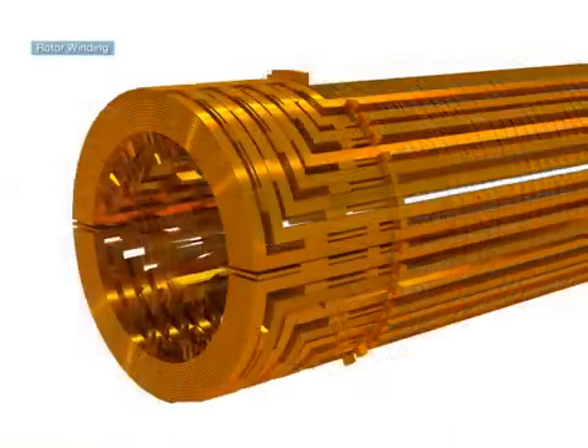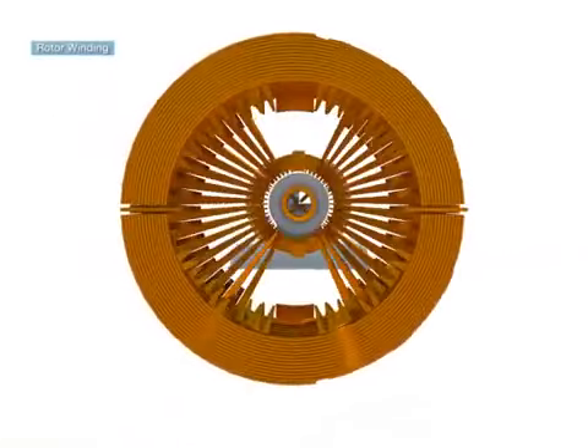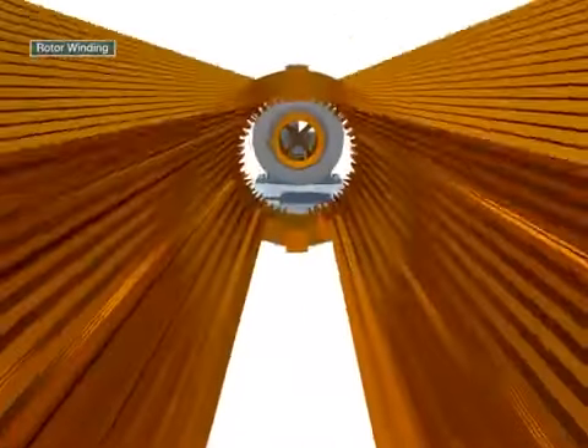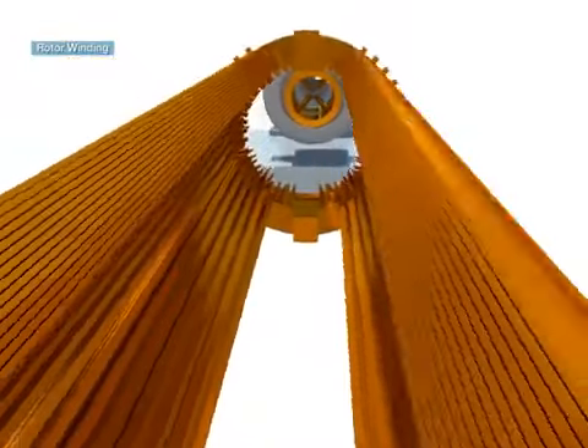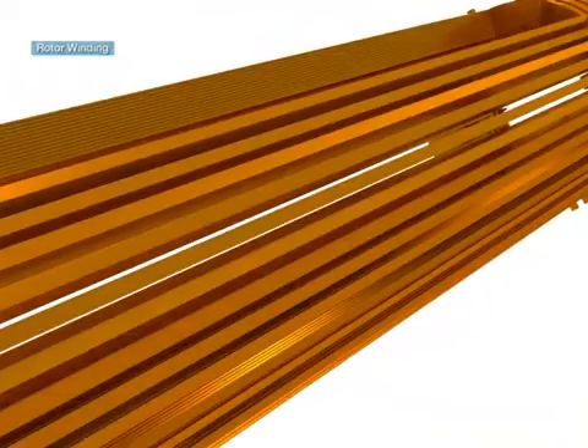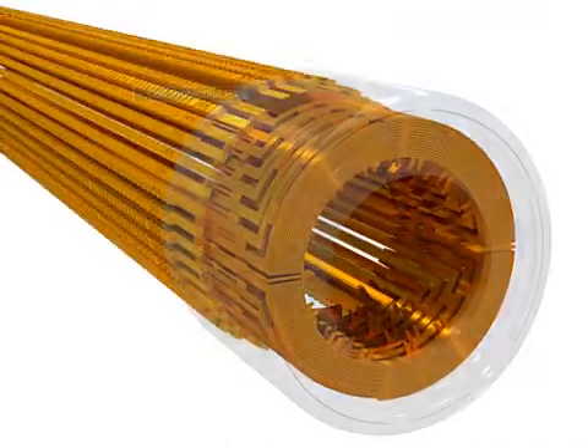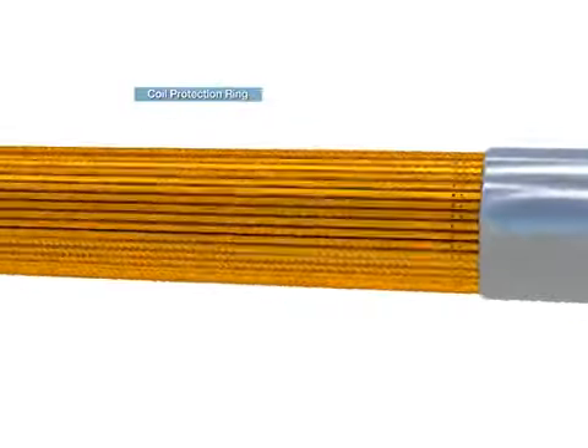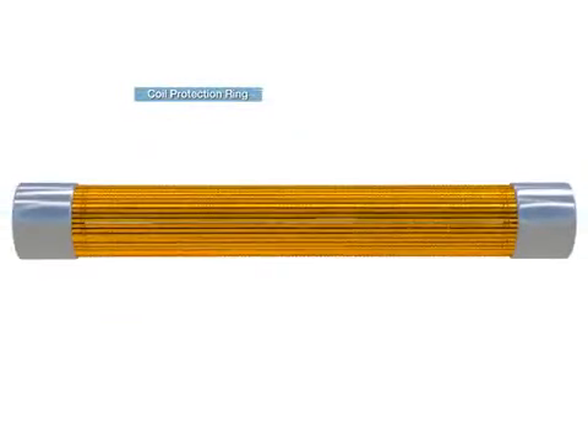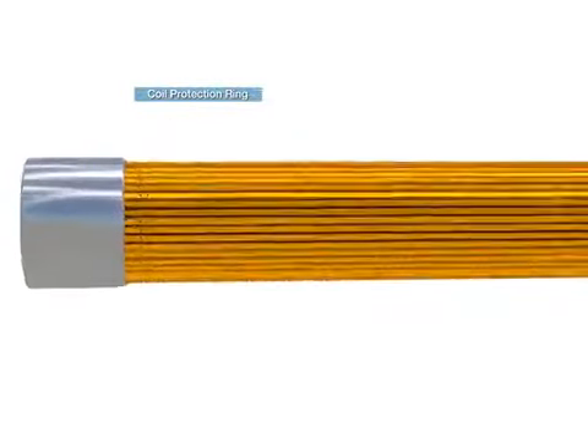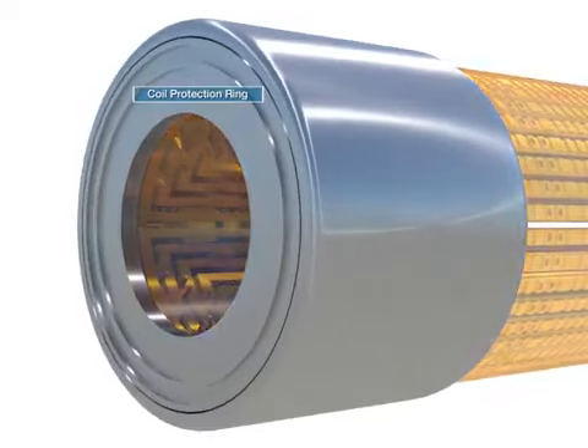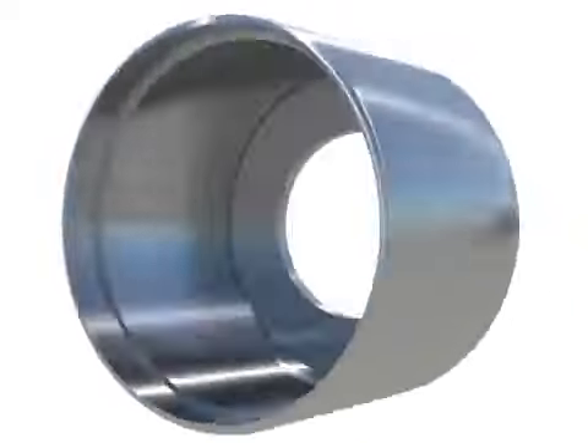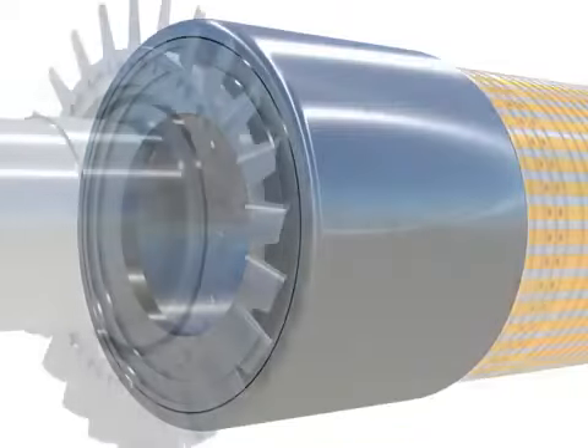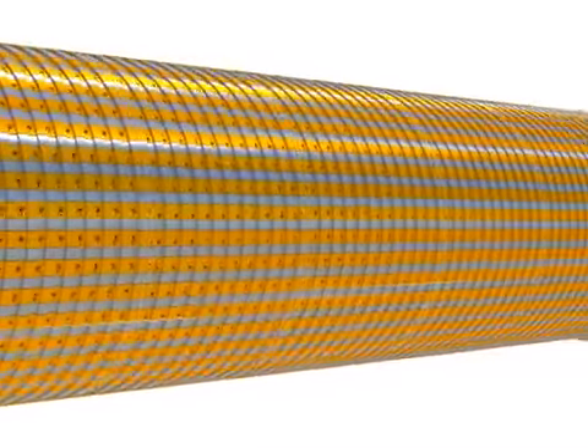The rotor winding is a copper wire with direct current to make the rotor shaft a field. The coil protection ring is a cylinder installed at the rotor end, shrink-fitted to prevent the coil from moving away due to strong centrifugal force, which is caused by high-speed revolution.